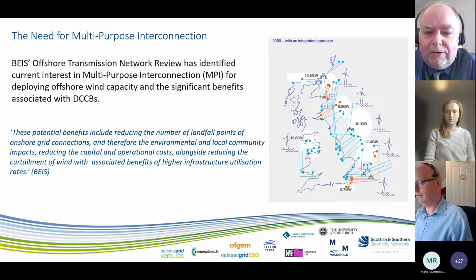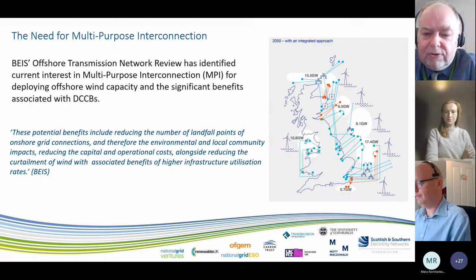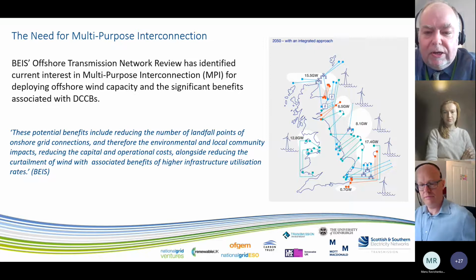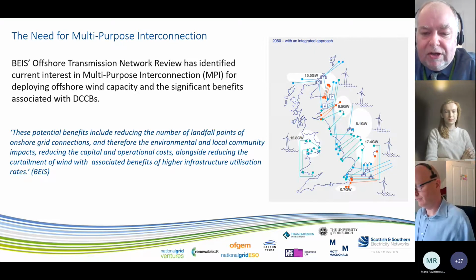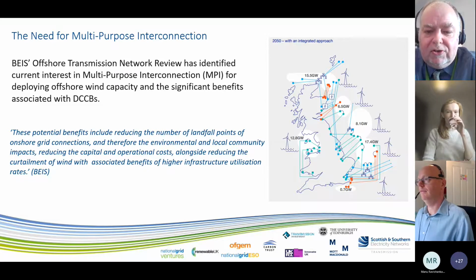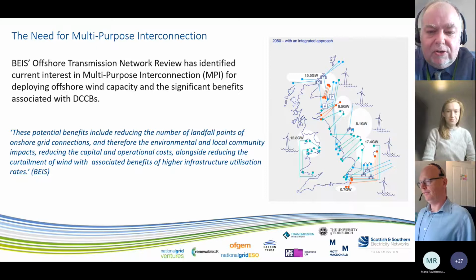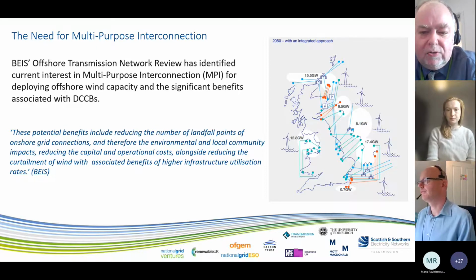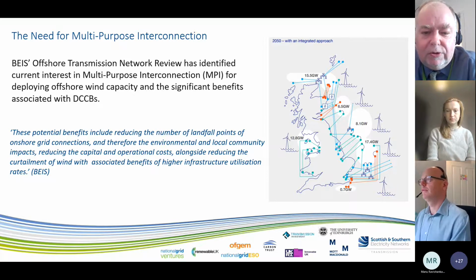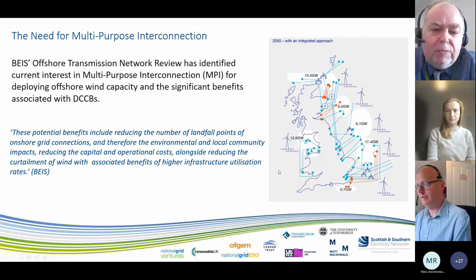Where you see squares with lightning bolts within them, these were DC hubs. On the south coast in red, there are a number of HVDC interconnectors which have intermediate offshore points, which would be multi-purpose interconnectors, which as they scale could consider using DC hubs. Essentially what DC hubs allow for is, much as the AC system, a rationalization of assets, so that each supply of generation to point demand doesn't require discrete circuits of its own, but can be pulled together in a network that maximizes capability and minimizes infrastructure.